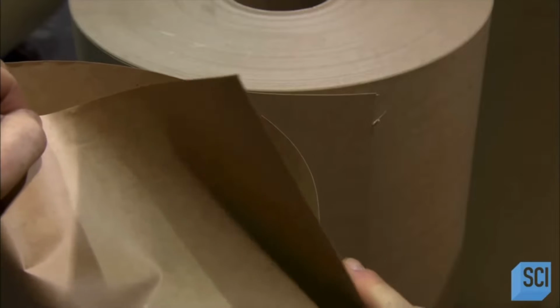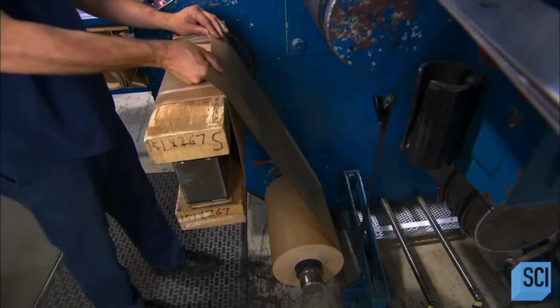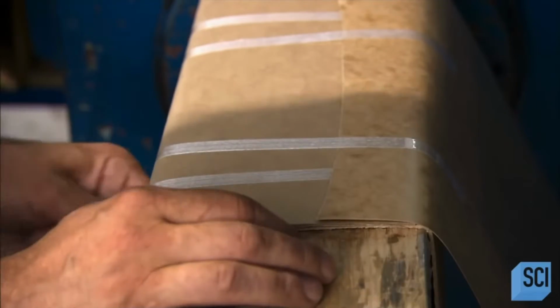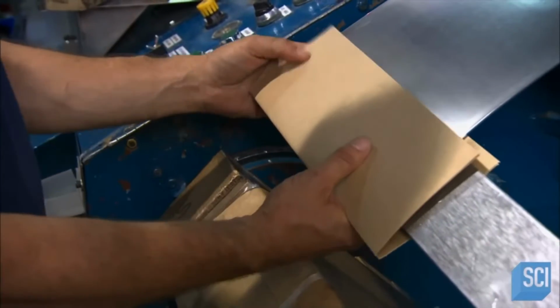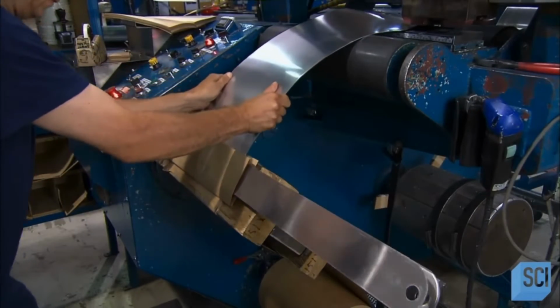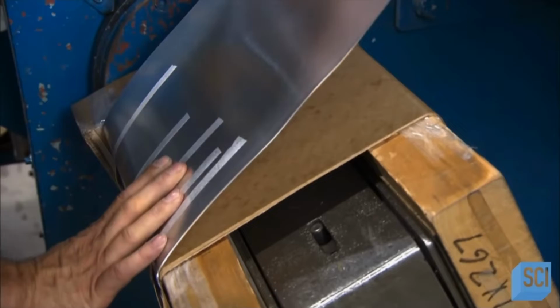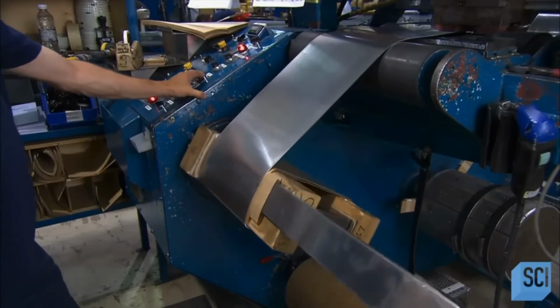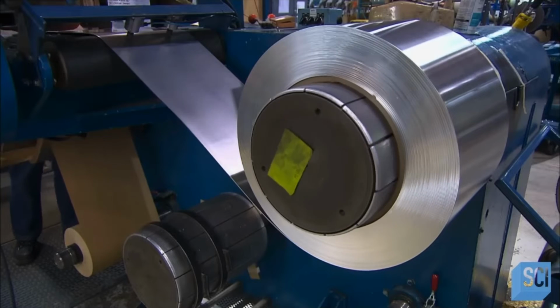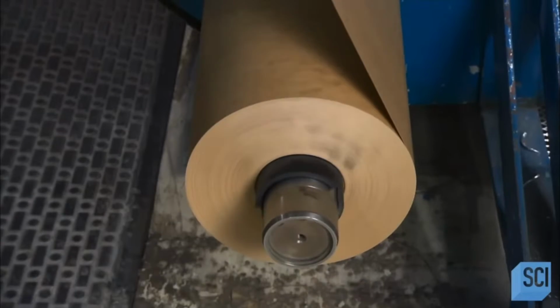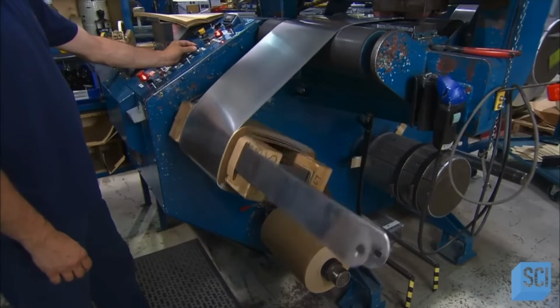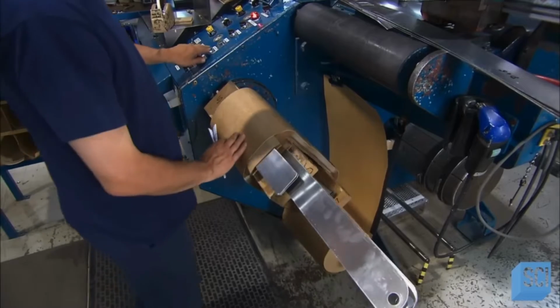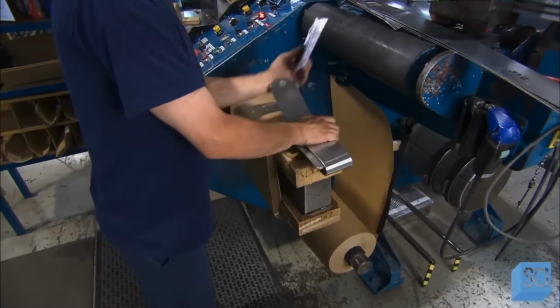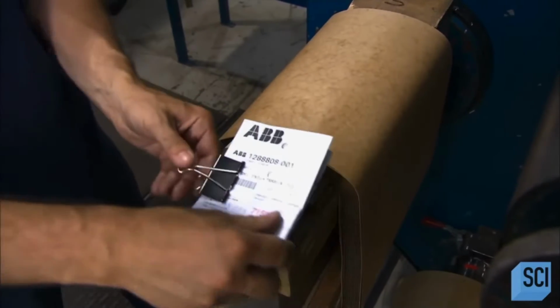To build a transformer, workers start by taking paper that's coated with epoxy glue and tape it to a wooden block. Next component, an 1/8 of an inch thick aluminum strip. It's a metal that can withstand the heat that a high voltage current produces. As the block is rotated, the paper and the aluminum strip are wrapped around it. An aluminum bus bar, called the low voltage lead, sends low voltage current out from the transformer. Workers fold the lead and move the unit to another rotating block for more wrapping.